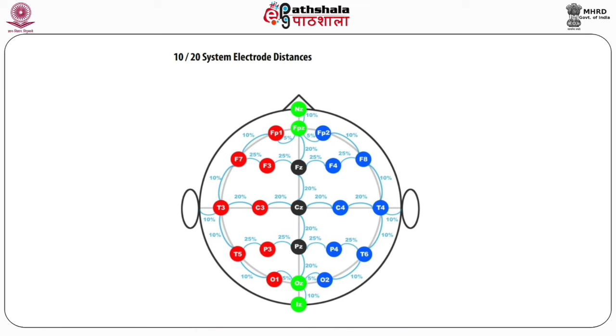Once we define a montage, which is basically defined based on the combination of electrodes or the electrode net, we need additional things. EEG as a biopotential is very low amplitude, around 0.1 to 100 microvolts, as opposed to something like ECG and EMG, which would be around 100 to 1000 times higher in magnitude, in the 1 millivolt range. Thereby we need a specialized amplifier, in this case something called a differential amplifier, which would specifically amplify what we call the amplitude range and the frequency range of the EEG.